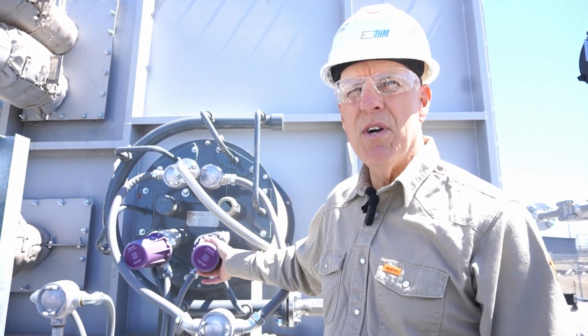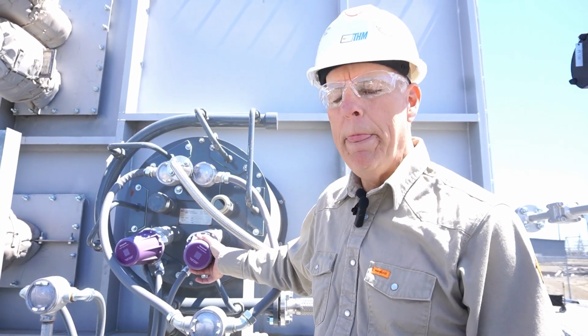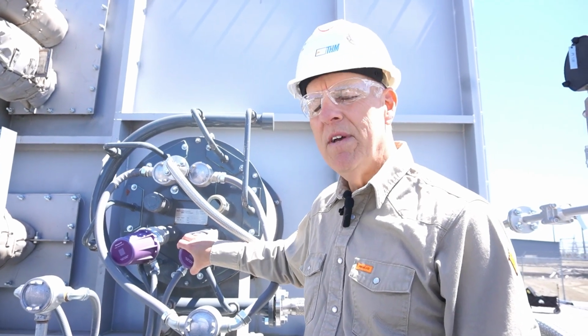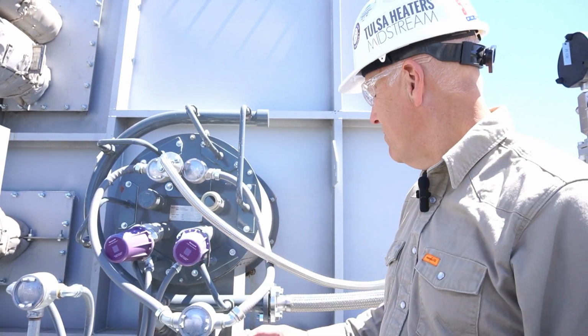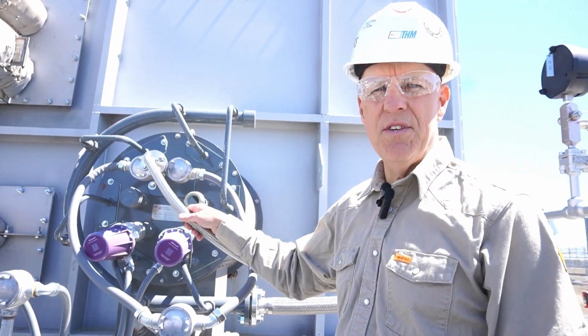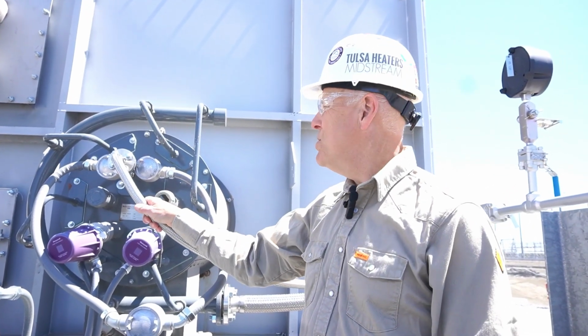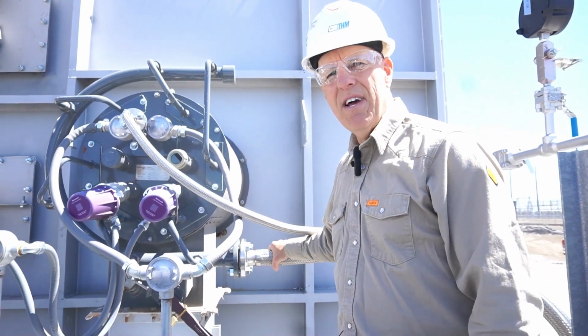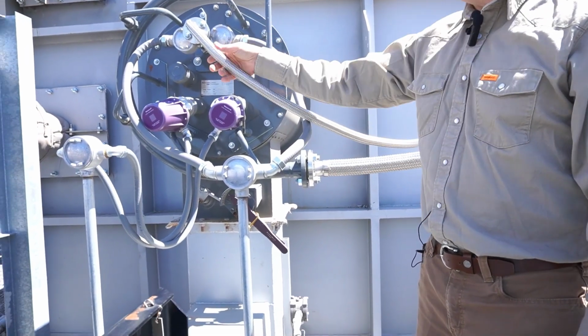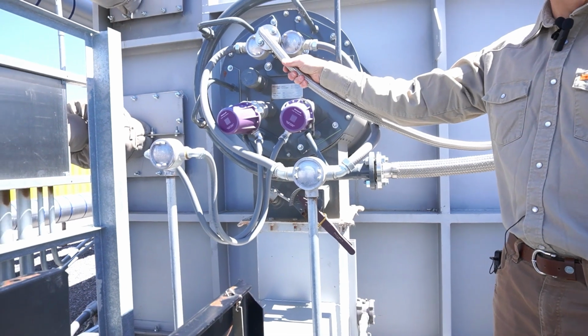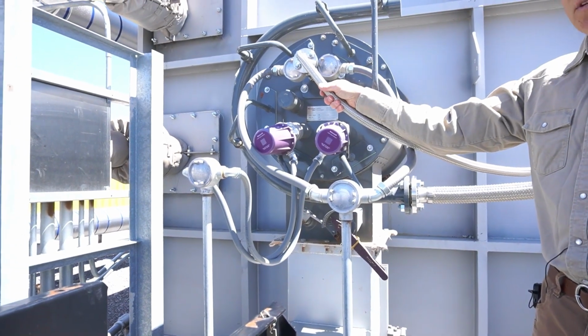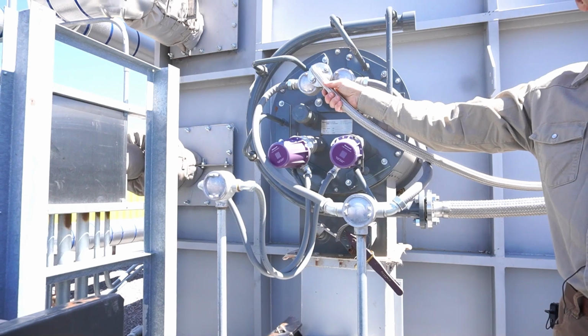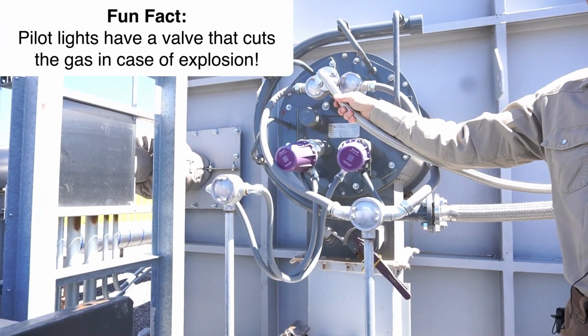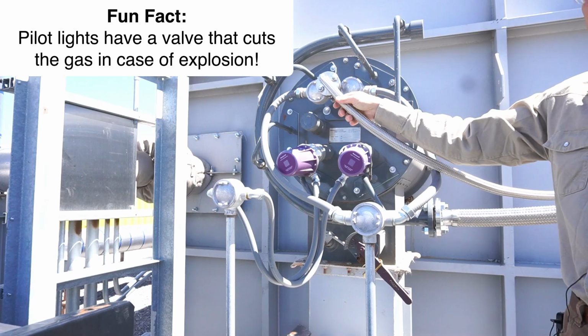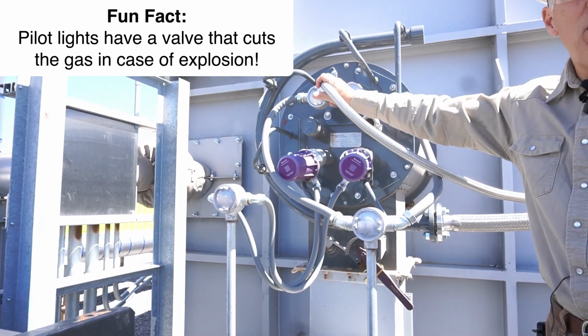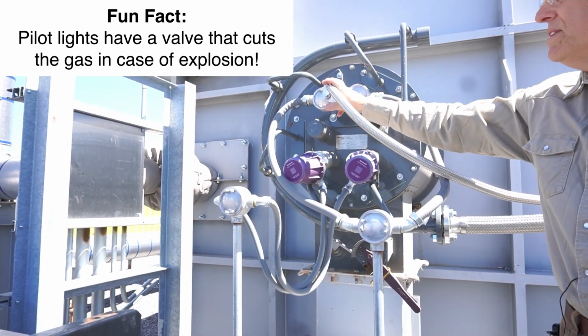And there's two of them, because one is looking at the pilot and the other is looking at the main flame. So what that means is, hey, I've got two different fuel sources. This is the pilot gas, smaller. This is the main gas, obviously it's bigger, okay? So the pilot is used for lighting the burner, and sometimes it's actually left on. Sometimes it's turned off. It just depends on what the customer preference is.